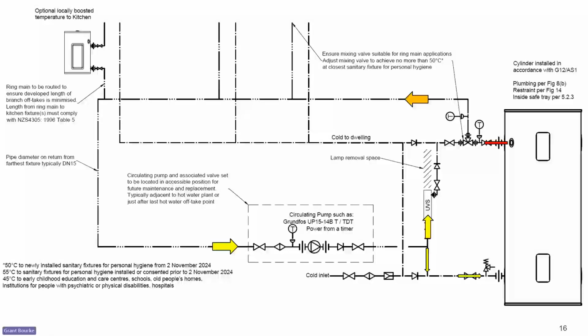And with that water going back to the cylinder, the mixing valve allows some hot to come out. And it's the mixing valve that's controlling all this. So we've got a little bit of water going in the tank, a little bit of hot coming out. And the balance of the recirculated water joins up with the hot, which tops its temperature up, and we're back to the temperature we started from.